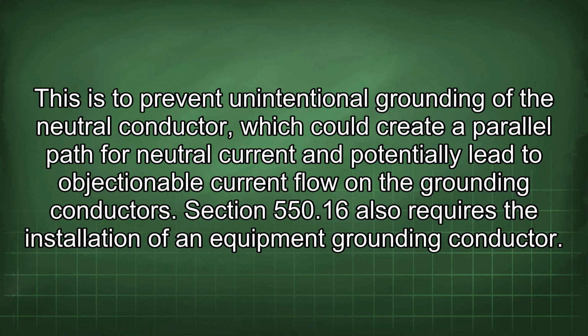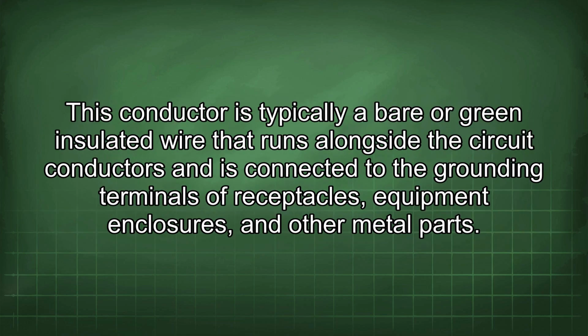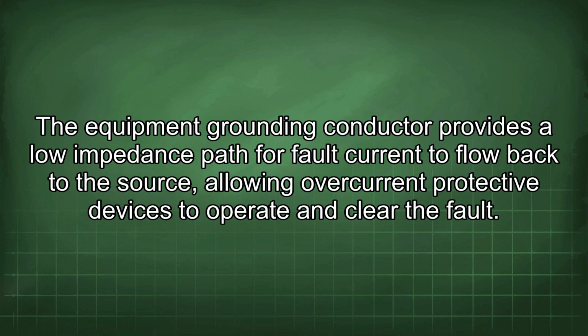Section 550.16 also requires the installation of an equipment grounding conductor. This conductor is typically a bare or green insulated wire that runs alongside the circuit conductors and is connected to the grounding terminals of receptacles, equipment enclosures, and other metal parts. The equipment grounding conductor provides a low impedance path for fault current to flow back to the source, allowing overcurrent protective devices to operate and clear the fault.